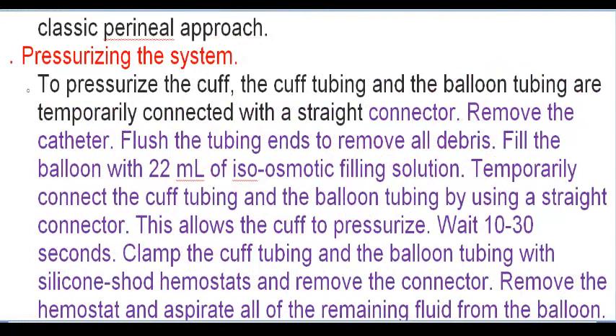Pressurizing the system. To pressurize, the cuff tubing and the balloon tubing are temporarily connected with a straight connector. Remove the catheter. Flush the tubing ends to remove all debris. Fill the balloon with 22 ml of isoosmotic filling solution. Temporarily connect the cuff tubing and the balloon tubing by using a straight connector. This allows the cuff to pressurize. Wait 10 to 30 seconds. Clamp the cuff tubing and the balloon tubing with silicone-shod hemostats and remove the connector.